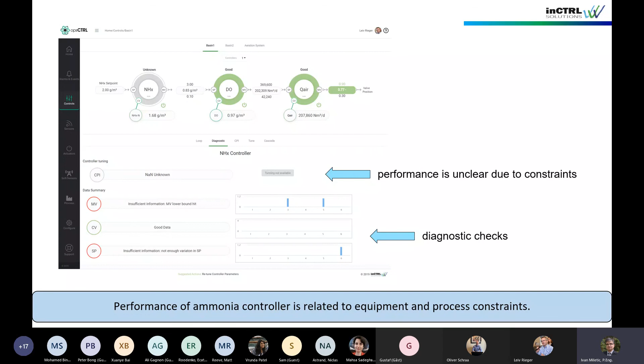In this case, for an ammonia controller, we're not able to really assess the performance because the diagnostics indicate a lack of information in the data - there's not enough variability in the set point, suggesting you might want step changes to move the controller around, and the manipulated variables have hit certain bounds. We can assess in real time the performance of the controller and the quality of the incoming data relative to the controller's expectations.